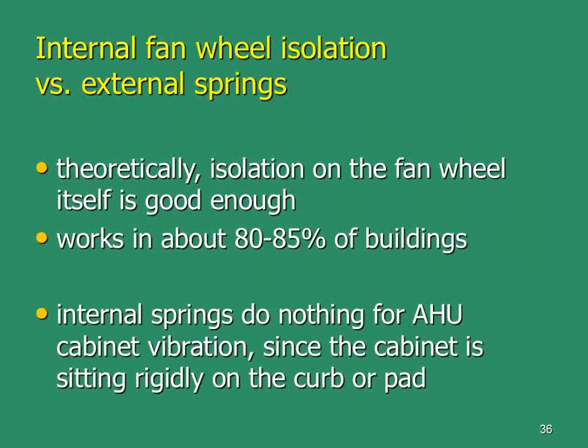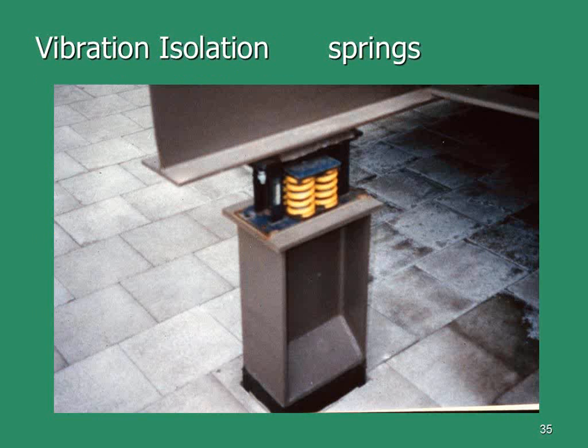Vibration isolators: springs are a good thing. Pads, cork, felt, rubber—usually not so much. You'll often see them in different colors because you need a different rating for each corner of the equipment, since they have a weight distribution. You have a heavy end and a light end—you can't use the same spring on all four corners. One end will be too squishy, the other too stiff.